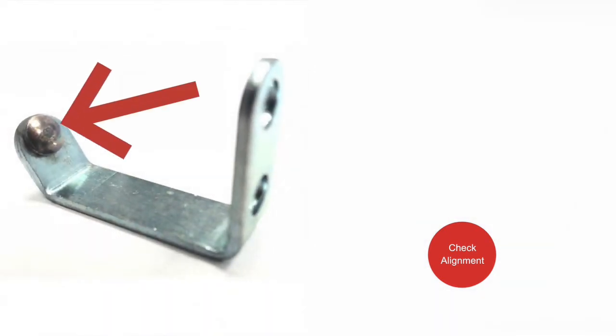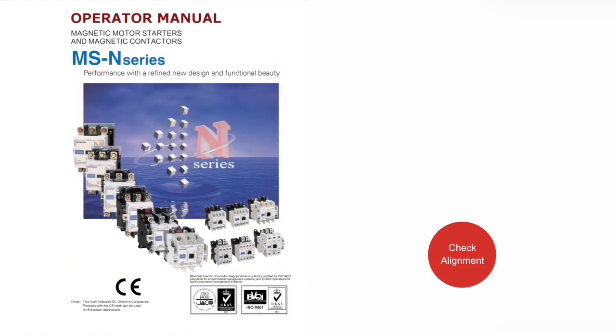Sometimes the contact pads are crowned or have a radius like this contact. This is not a concern as long as the alignment is good. You can push down on the movable contact holder to check the alignment as it mates with the stationary contacts. There should be as much contact as possible. If misaligned, the contact alignment should be adjusted according to the manufacturer's instructions.